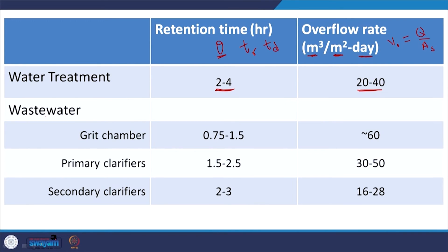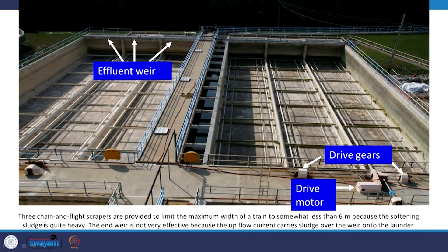Typical design values: for water treatment, retention time is 2–4 hours. For wastewater treatment, grit chambers have short retention times and high surface overflow rates since we only remove large inert particles. Primary clarifiers have increased retention time and lower overflow rates. Secondary clarifiers, which follow the biological process and handle floc-forming bacteria, have even higher retention times and lower overflow rates.